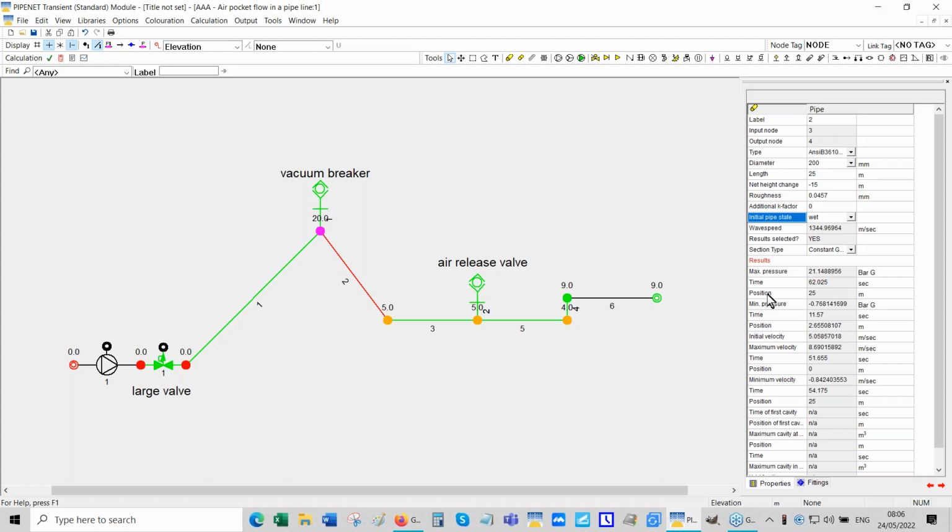We call it priming. The pipes get primed gradually, one by one. But the PIPENET dry pipe model is not limited to that. A pipe could also start with a wet state, as it is here, and then it can become dry, and it can become wet again.